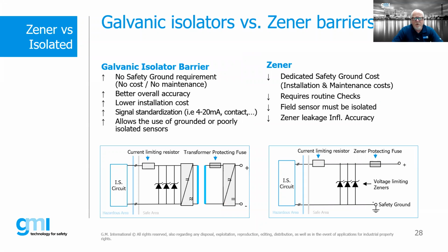So people ask, I'm telling you all this great and wonderful stuff about galvanically isolated versus Zeners, right? Well, there are some trade-offs. There's cost benefit analysis. As I mentioned, the largest advantage of using a galvanically isolated barrier is not having to have that safety ground. That can be a significant cost savings, and it also saves all the maintenance required to ensure that we do have a good ground. Generally, we have very good accuracy. And again, it allows the use of grounded or poorly isolated sensors. With Zeners, again, we do have to have that dedicated safety ground. It does require routine checks.